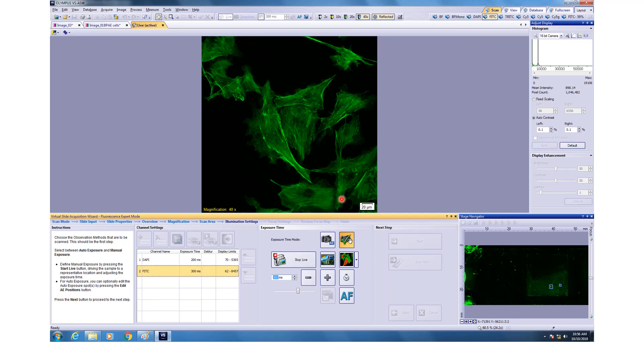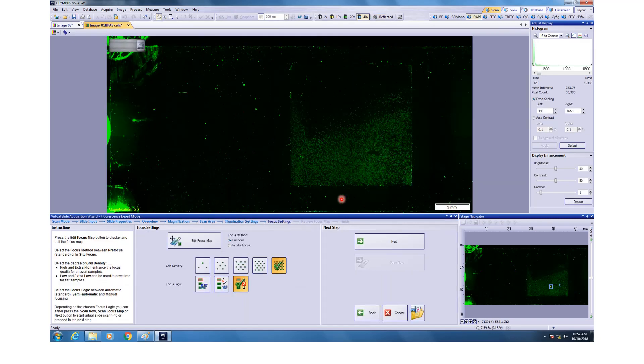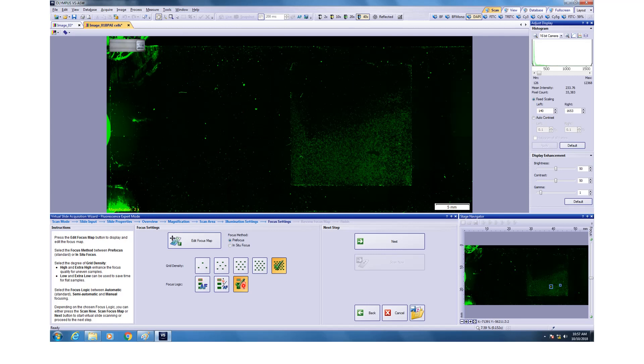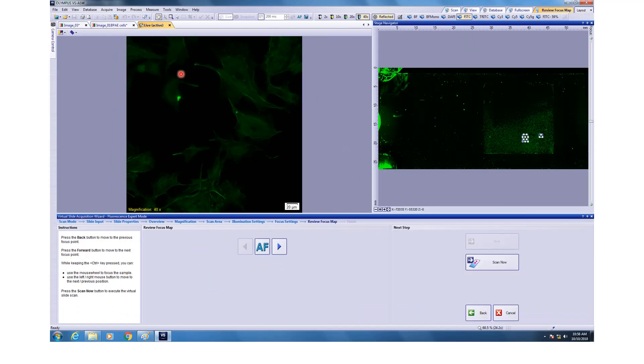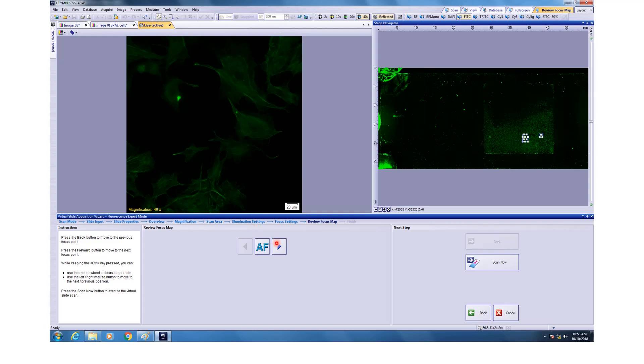After this is done, now it will ask what kind of focusing would you like to do. You can do auto focus. Because I had very less number of focal points in this image, about 10 to 12 of those, I will for now use manual focusing. If I check this option and click next, then this kind of window will open where I can use my Z control to actually find the right focal plane and click next. Or I can do auto focus and it will also use the auto focus logic. Sometimes it works, sometimes it doesn't work. That's why I did manual. Once you have done for all the points, then you can click scan now.